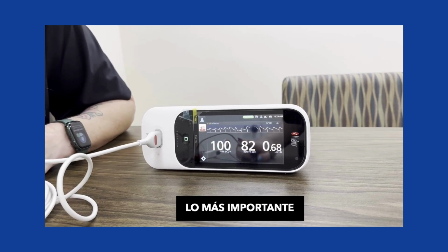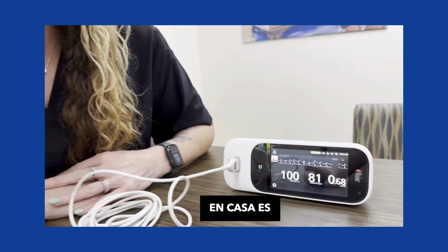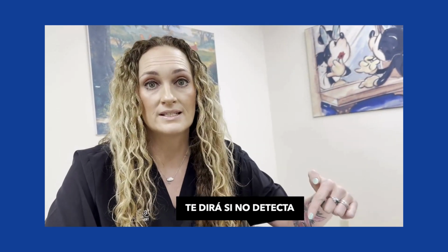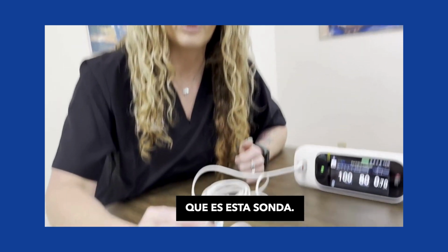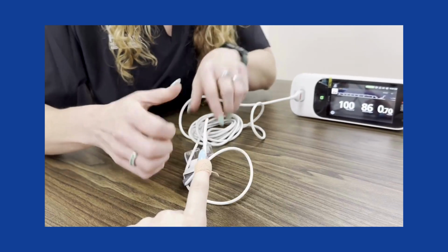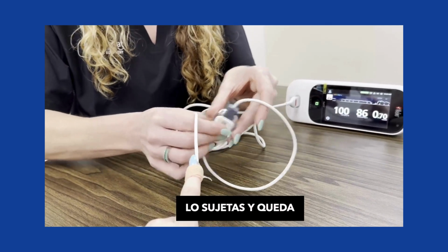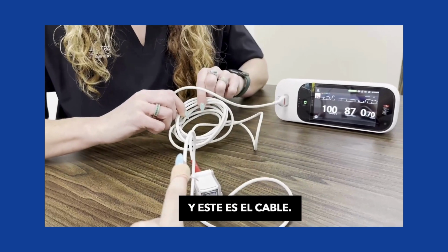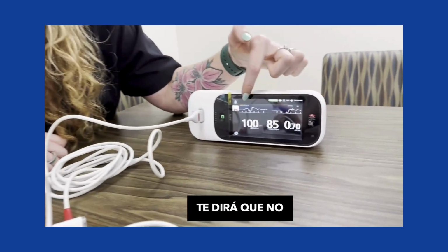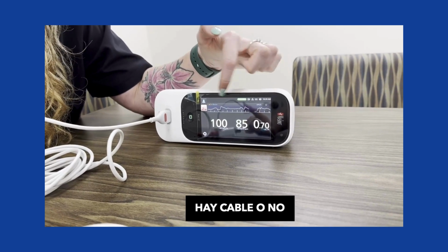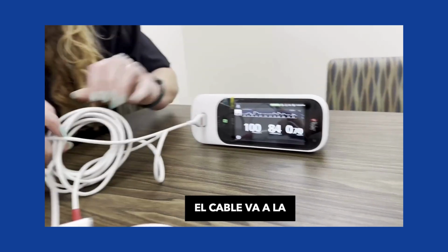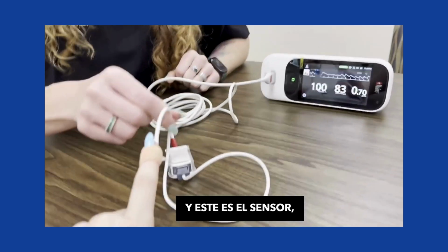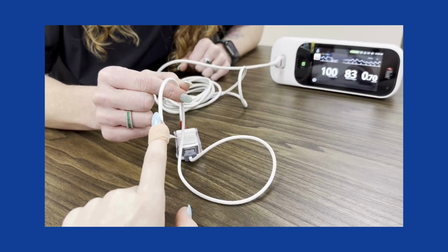But the biggest thing for you at home when you're trying to troubleshoot is read the verbiage at the top of the screen when there's an alarm going off. It will literally tell you if it doesn't detect the sensor, which this is the probe sensor. This is this thing. And again, once you connect it, you just clip this and it holds it in place. And this is the cable. So the verbiage will be different. It'll either tell you there's no cable or no sensor. So the cable is the piece that goes to the machine itself here. And this is the sensor, the pulse ox probe.